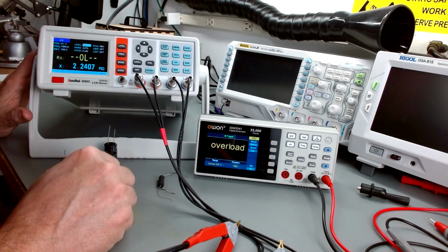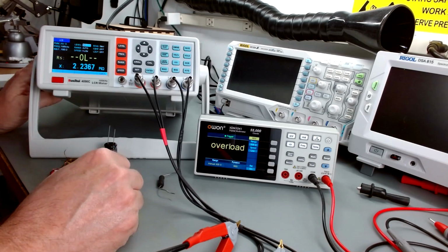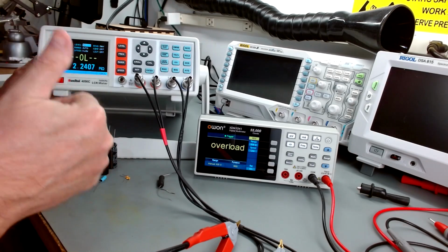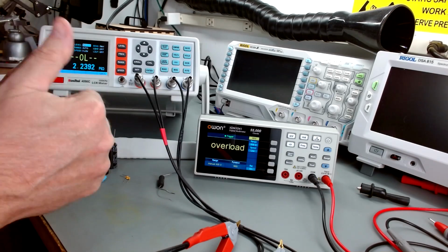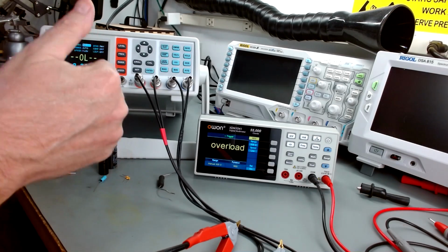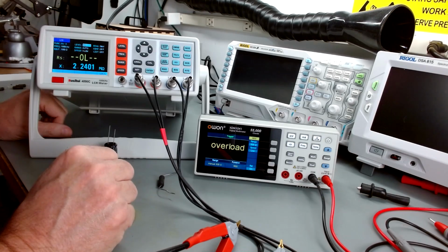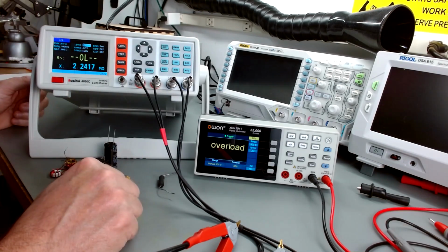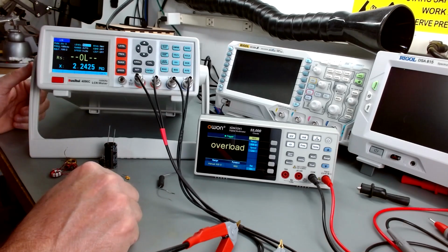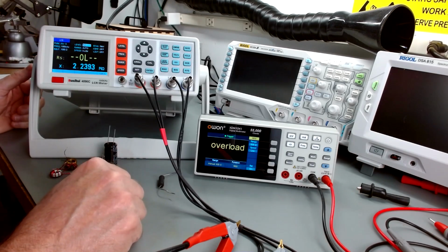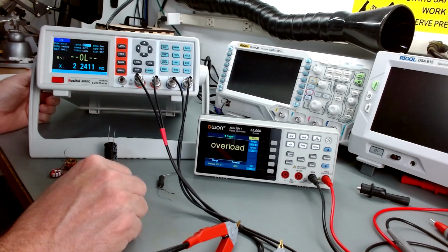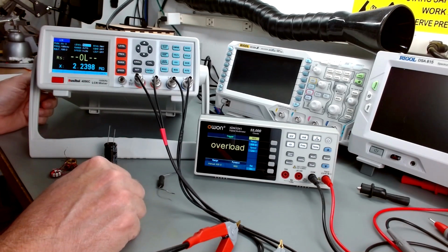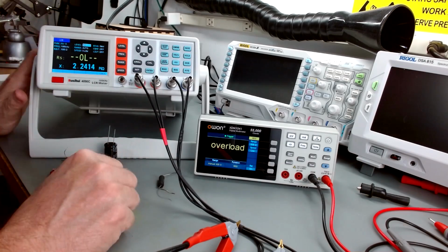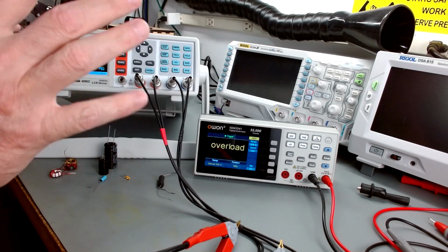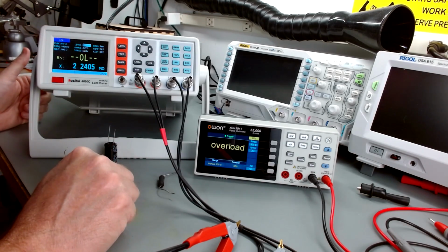And the problem with calibration is the speed. It comes up and gives you a 20 count for both the open and closed calibration, but that's not seconds. It takes about 45 seconds each one of them to run through. So I'll give you a demo of that at the end of the video. That way I can run through and time lapse it where you don't have to sit and watch the whole thing. But you're basically looking at about 1.5 to 2 minutes to calibrate this to get it ready to go if you change anything. Now, most people, that's not going to be a big deal.